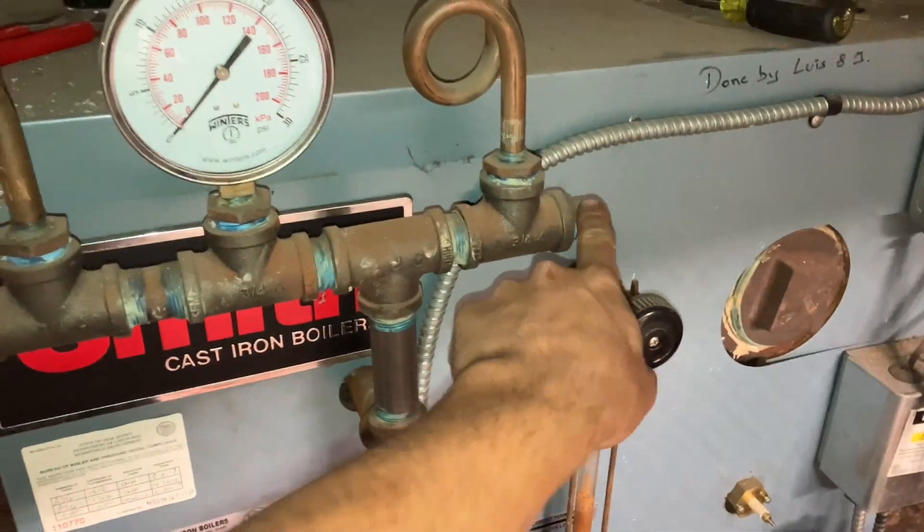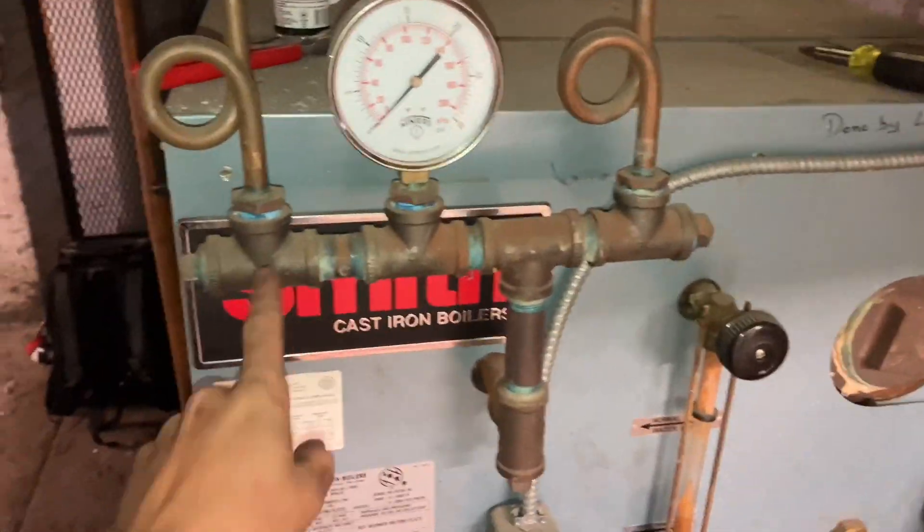While I'm waiting for that to drain, I'm gonna open up my Pressuretrol loop and make sure that this is not plugged up. And to be clear, when I say drain it, I mean drain it just below the probe, not the whole boiler. That would be pointless.